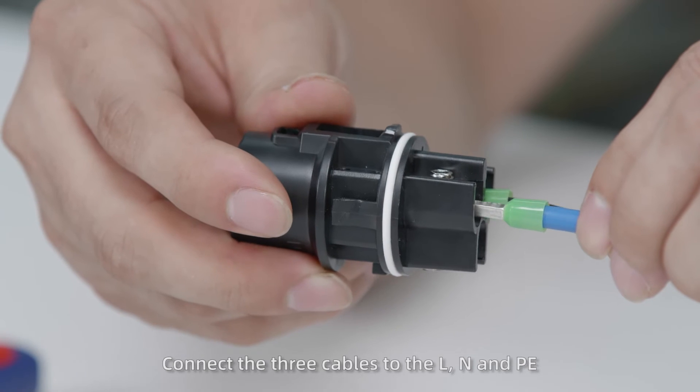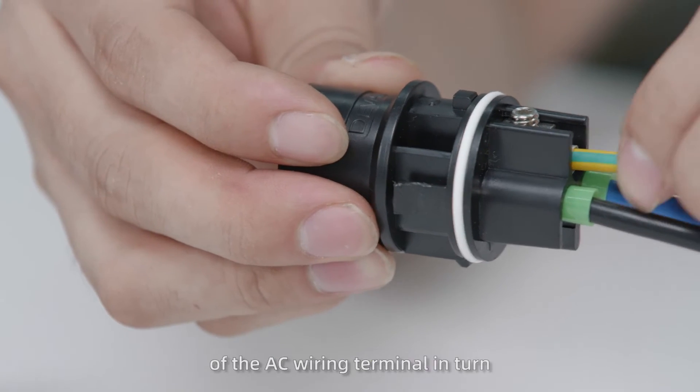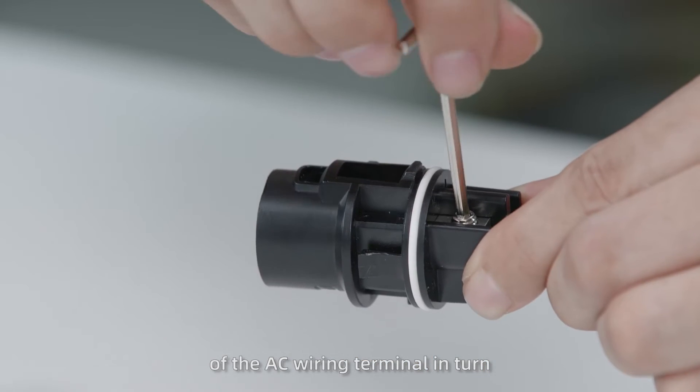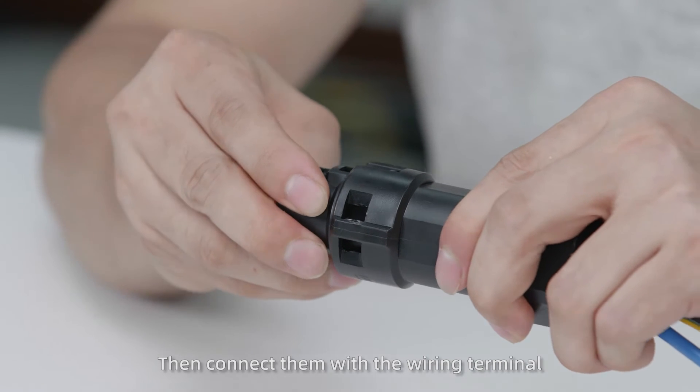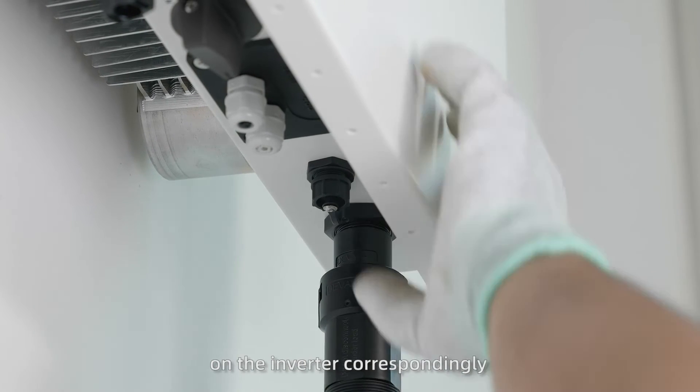Connect the three cables to the L, N, and E of the AC wiring terminal in turn. Fasten them with a screwdriver and tighten the waterproof lock. Then connect them with the wiring terminal on the inverter correspondingly.